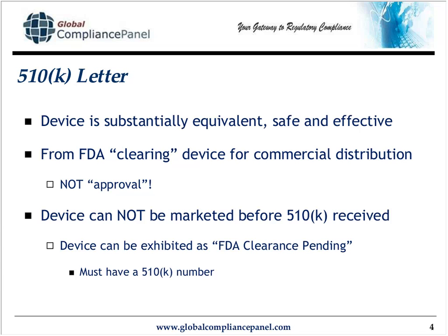And it really doesn't matter what people say around the, I guess there's really no water coolers anymore. Let's call it the Keurig device. However, when people get used to using terminology, they may use it elsewhere where it's not that good. If you go to a trade show and you advertise your device as approved for commercial distribution, you will probably receive a visit from the FDA inspectors who routinely walk the floor at trade shows.